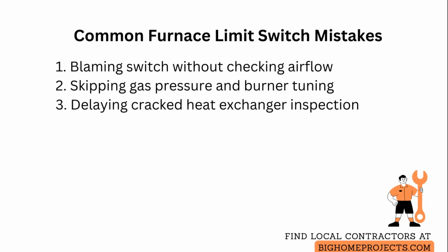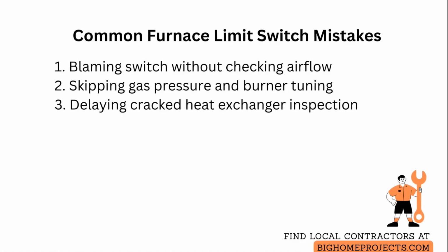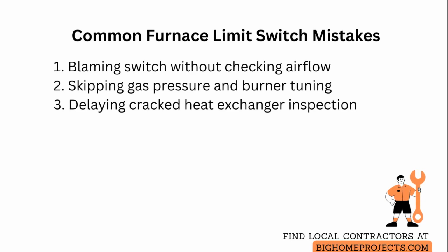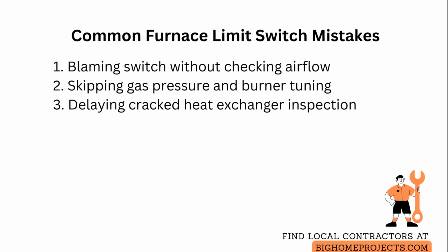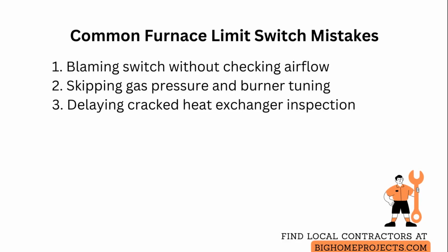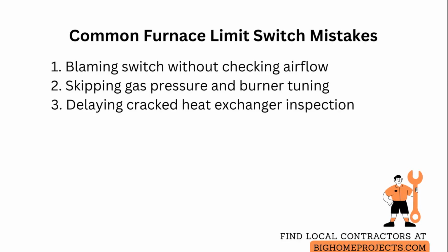The three most common mistakes are blaming the switch itself without checking airflow first, which you can avoid by always inspecting filters and vents before replacing parts. People often ignore proper gas pressure checks and burner tuning, and the short fix is to schedule a licensed technician to measure pressure and adjust burners rather than guessing.